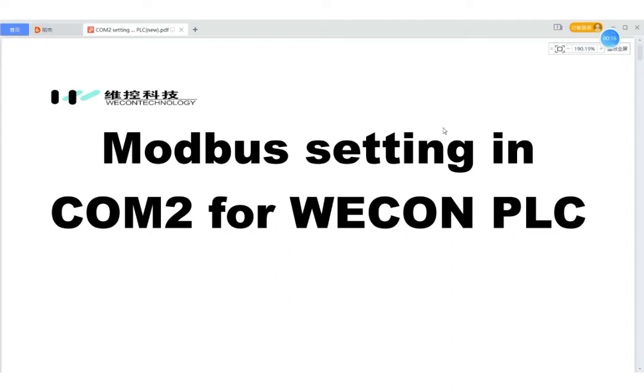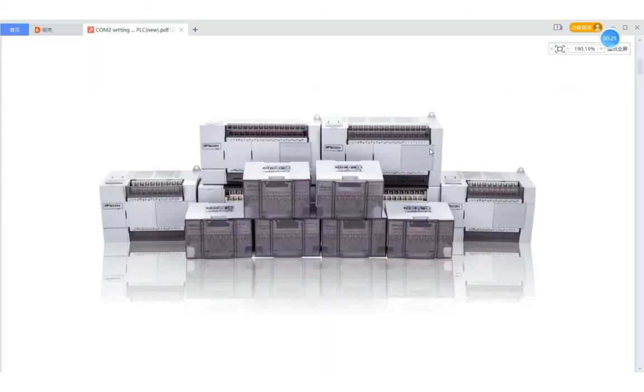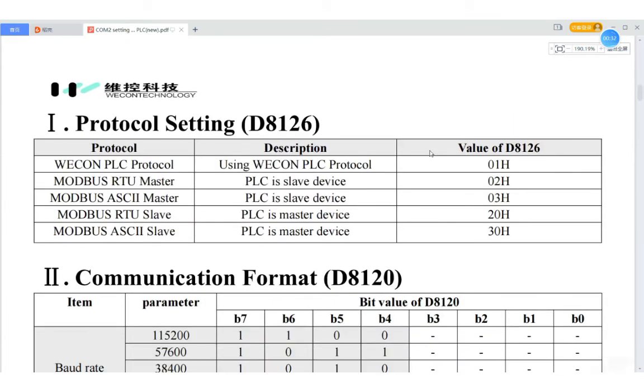LX3V COM2 can also support WECON protocol and the Modbus protocol. Now, two registers are very important for setting the communication. The first one is D8120, and the second one is D8126. D8120 is used to set the communication format, and D8126 is used to choose the protocol that you want to use. In total we have five communication protocols.